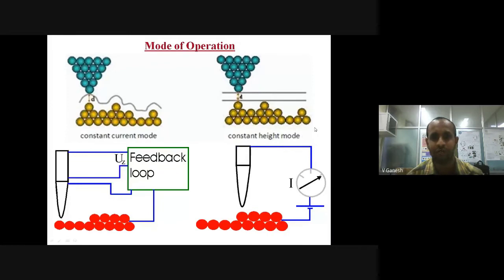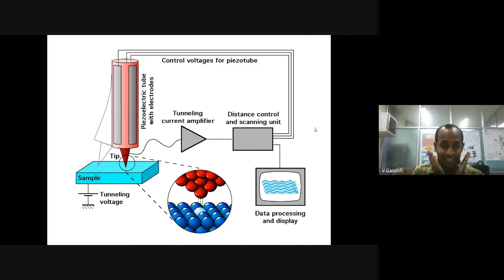If you look at the instrumentation behind the scanning tunneling microscope, the unit consists of a scanning unit with a sample substrate and a probe. When I say you move the tip as close as possible to the sample substrate, how do you achieve such movement? We cannot use our naked eye to move within a separation at the nanometer level. There are different ways to move the sample tip, such as using an inchworm motor or a tripod scanner.